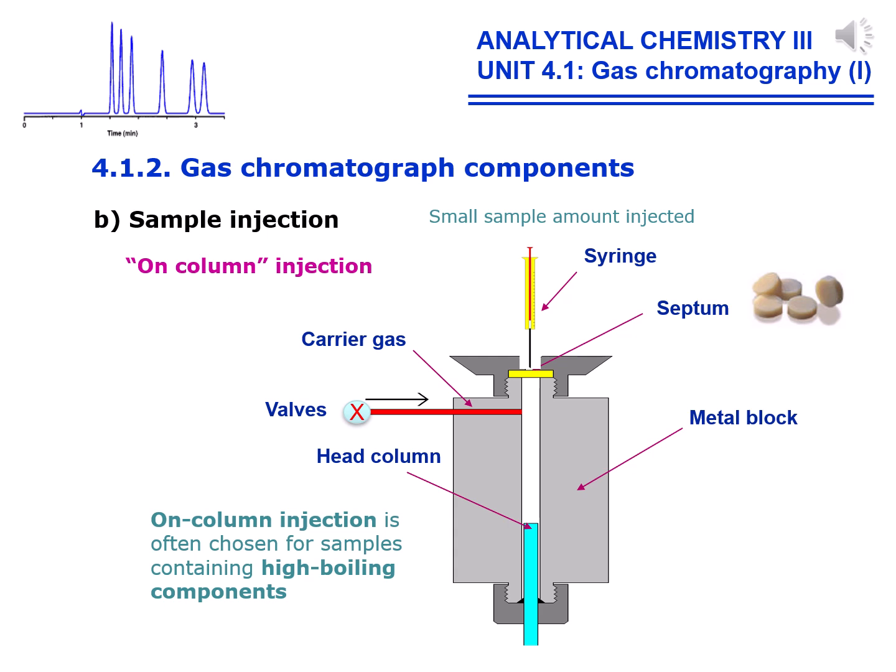The second basic component for a correct injection is the injection port installed. As we previously said, in gas chromatography all the components entering the column must be in the vapor phase. The design of the injector is critical to obtain good quantitative results in the analysis. With on-column injection, a liquid sample is directly introduced into the column with a thin injection needle. During the course of the temperature program, the vapor pressure of the solutes increases and the chromatographic process begins.